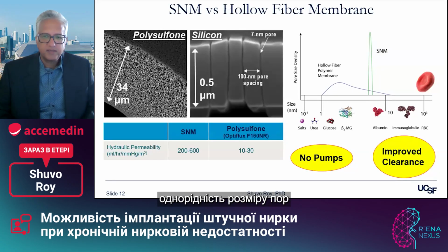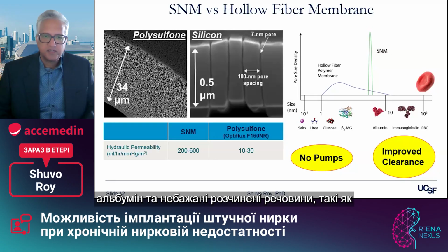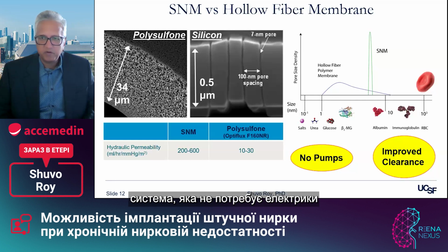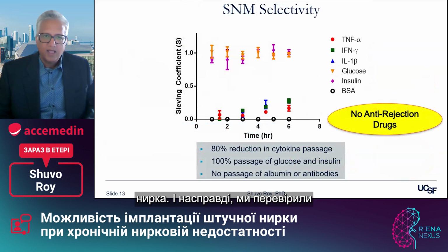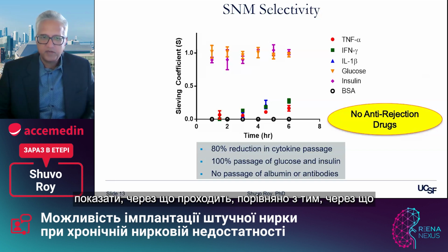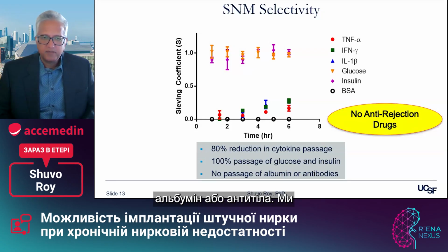Second, the uniformity of the pore size allows us to discriminate between desirable solutes, such as urea, and undesirable solutes, such as albumin. And by having a very sharp cutoff, our membrane allows that selectivity, which means we can actually achieve improved clearance. So our membranes make it possible to think about a system that does not require electrical power, but just relies on blood pressure, and then performs removal that's very much comparable to the native kidney. And in fact, we tested the selectivity of our membranes where we took a super physiological concentration of various biomolecules, including cytokines, insulin, glucose, albumin, and then we tested it on our membrane. And this graph shows the sieving coefficient, which is basically a way to show what goes through versus what doesn't go through. We had no passage of albumin or antibodies. We had almost 100% passage of glucose and insulin.